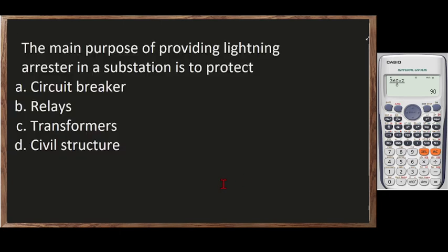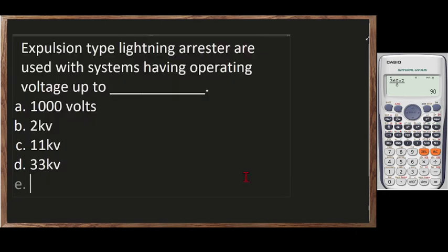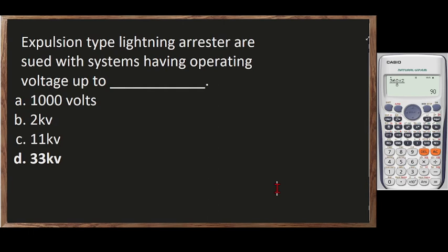The main purpose of a lightning arrester in substation is to protect the circuit breaker, relays, transformer, or the civil structure. Okay, the correct answer is letter C, no? To protect the transformer. Kasi kapag nasira yung transformer natin, the whole distribution line or distribution system will also stop or maaaring ma-cut off yung ating buong distribution system. Expulsion type lightning arrester are used with systems having operating voltage up to, okay, so the correct answer is letter D, 33 kilovolts.